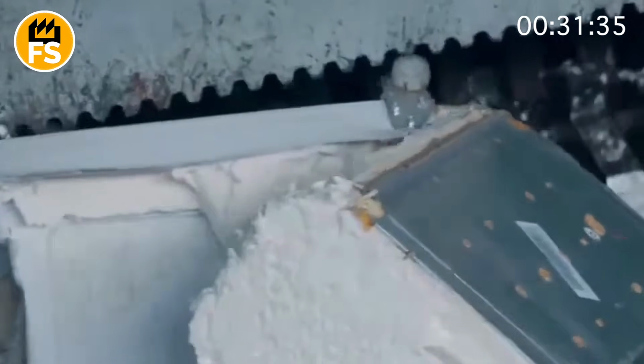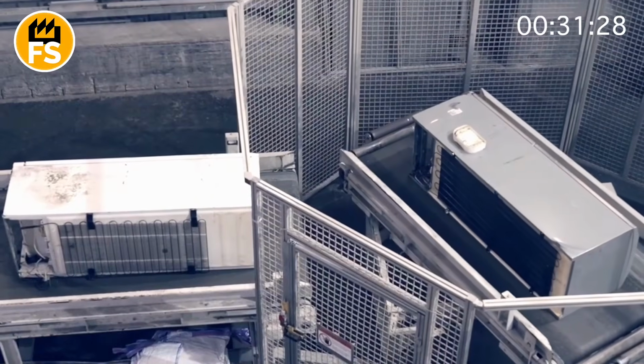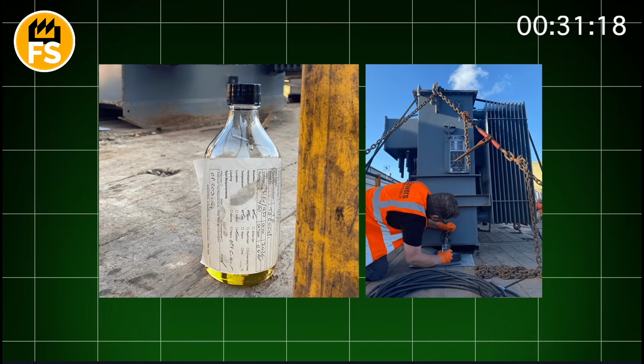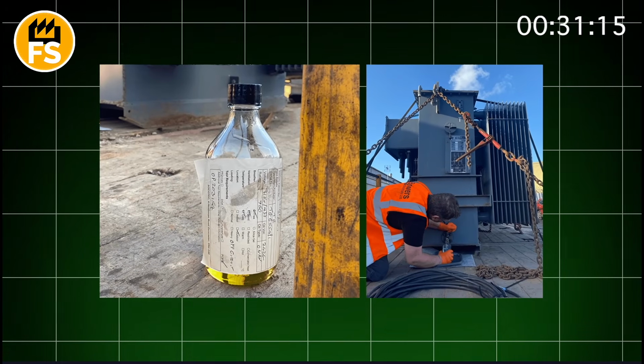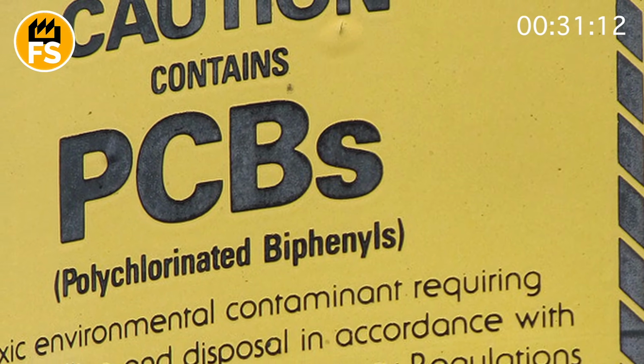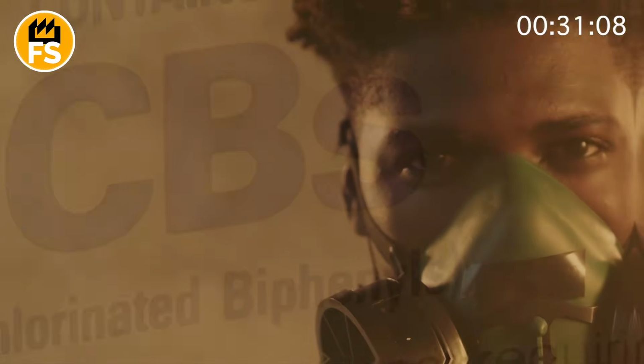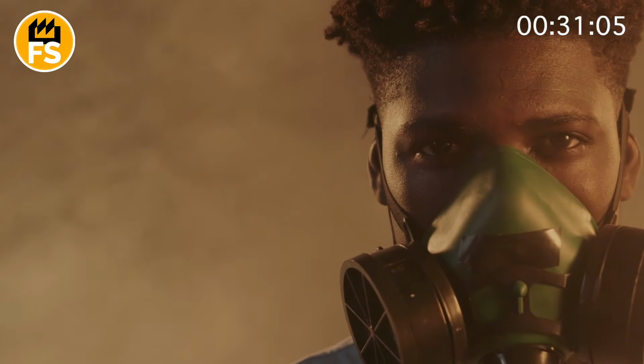As the transformer is broken down piece by piece on the dismantling line, the various resulting materials are carefully sorted and separated onto different processing conveyors and areas. Valuable metals like the pure copper windings are isolated into their own stream and sent for high-grade recycling. Steel casings, cores, and other structural steel components are separated for scrap metal recycling. Aluminum parts are directed to their specific recycling stream. But the key challenge, the hazardous legacy, lies with the contaminated materials. Any solid components that came into direct contact with the toxic PCB oil, internal insulation paper, wooden bracing blocks, contaminated gaskets, even metal parts that absorb the chemical, are now classified as hazardous waste themselves.